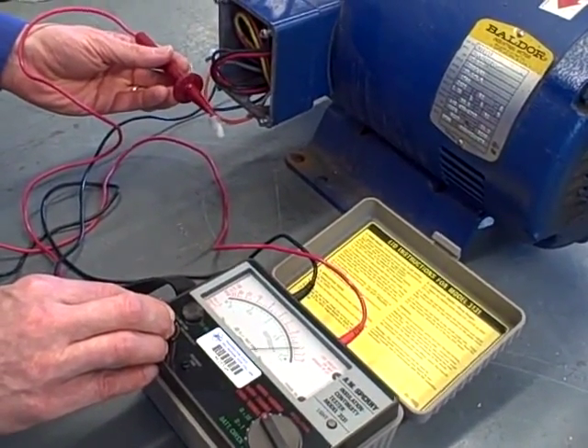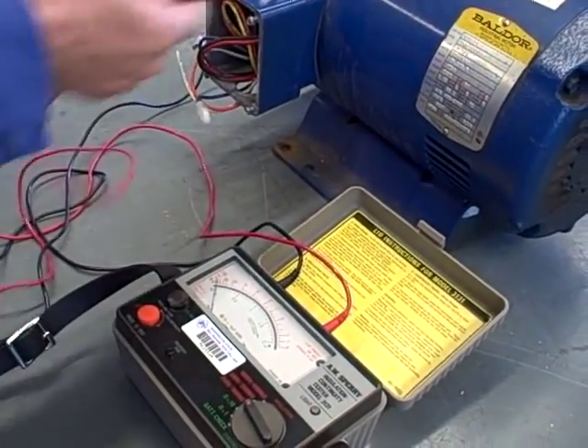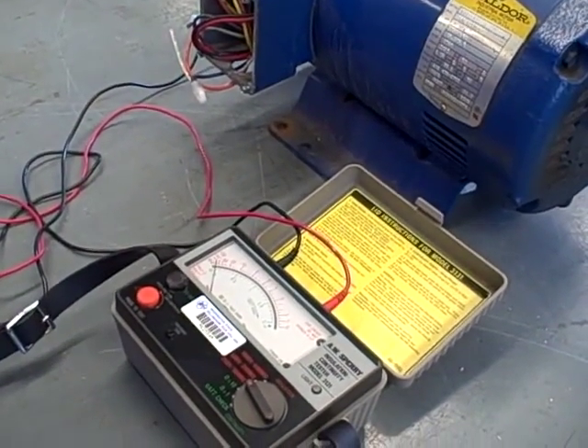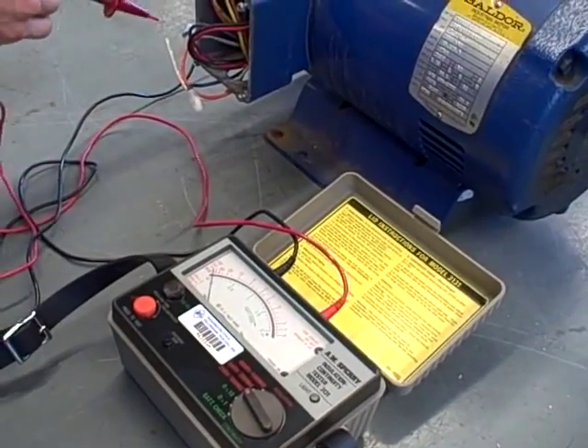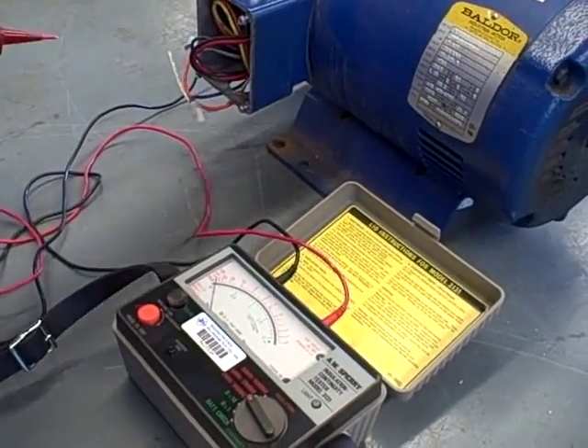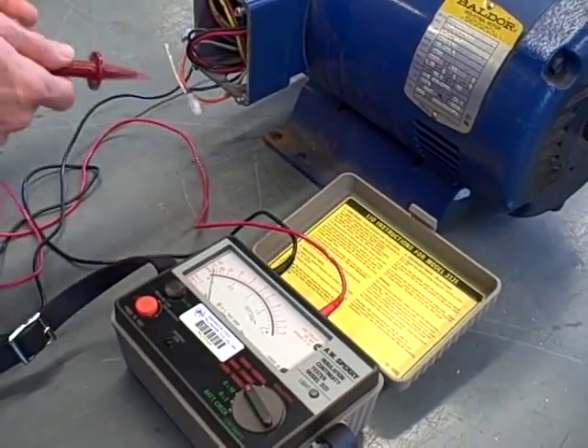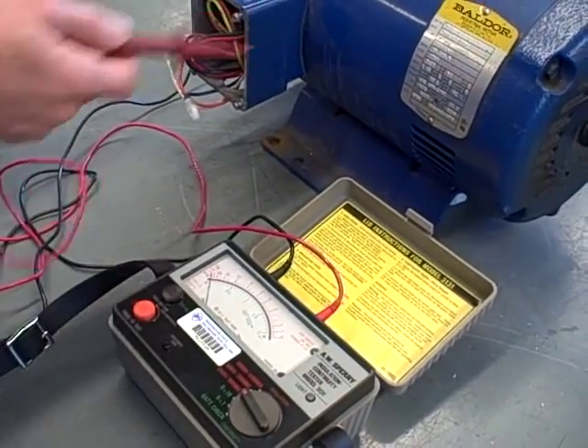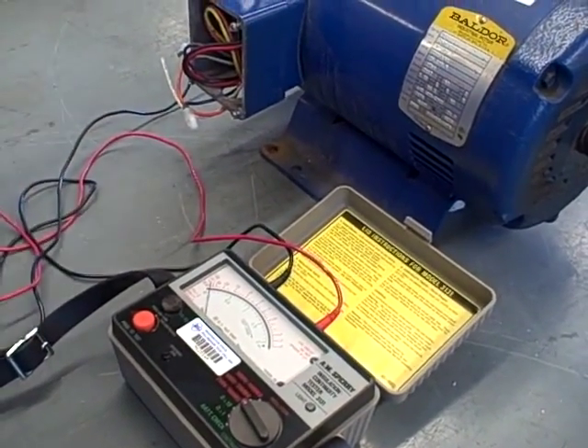Now I say of course, because it doesn't matter which winding in here has actually failed to ground. If I read to another one of these lines, I'm just going to read through one of the good windings to the failed one. So all I need is one ground fault anywhere in this motor. I'm going to read faulted to ground at any one of these lines.